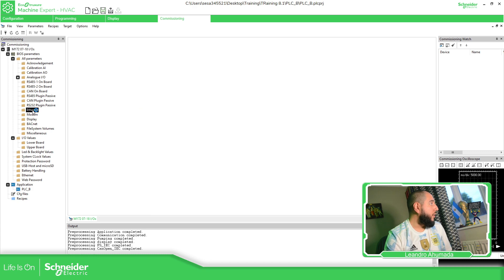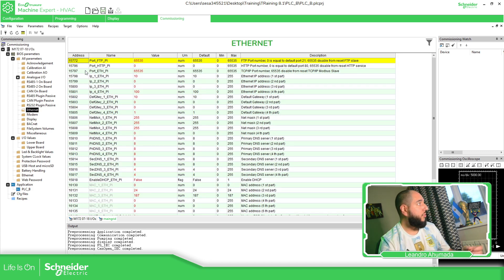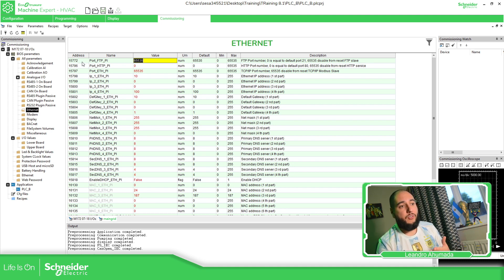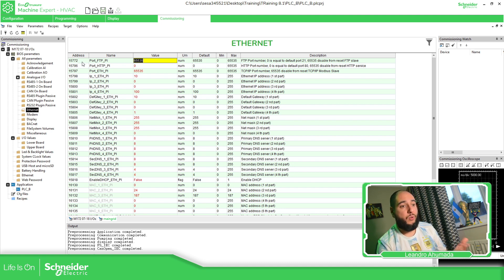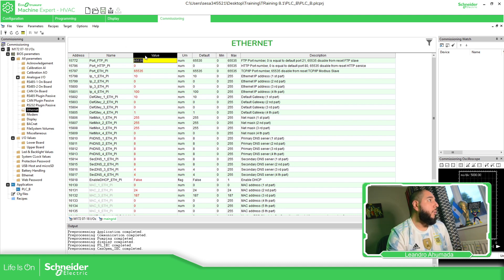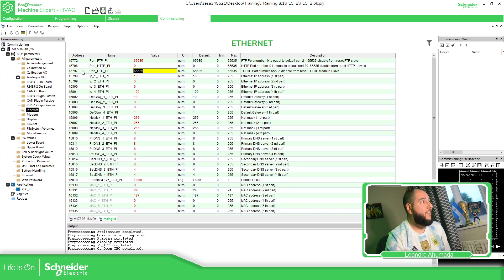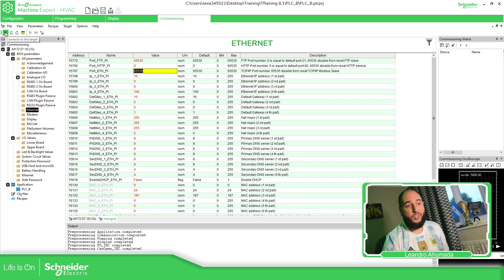If we go to Ethernet here, we should be able to see that the FTP port — if it's 65535, it means it's going to be disabled. If it's zero, it means it's using the default, which is port 21. So we can use 21 or not, but we can check it. If you're unable to connect, it means that the TCP port is disabled. So let's try to connect — I don't remember the status of this PLC, to be honest.